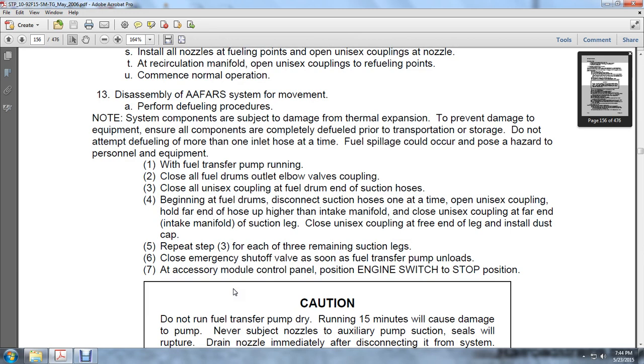With the fuel transfer pump running, close all the fuel drum outlet and elbow valve couplings. Close all unisex couplings at the fuel drum and on the suction hose. Begin at the fuel drums. Disconnect the suction hose one at a time. Open the unisex coupling.